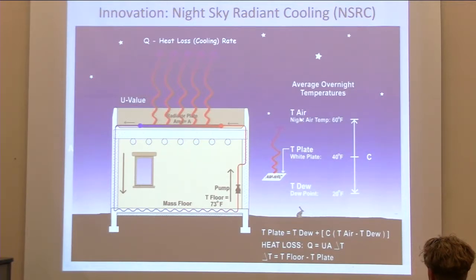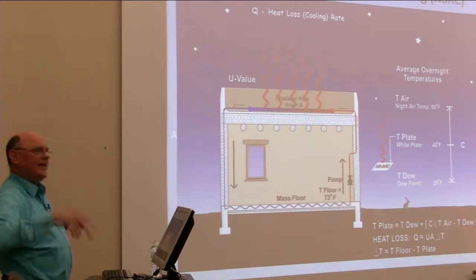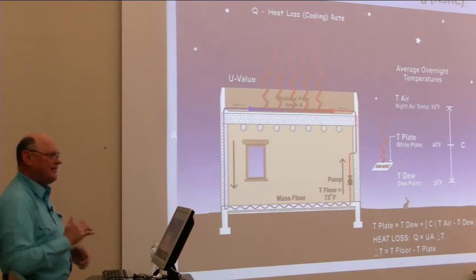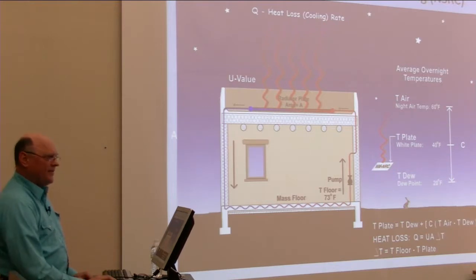You wait at night until the night is clear enough so that the plate temperature on this collector, the black surface on the collector, radiates away its heat to the night sky, and it radiates it so much faster than the air can reheat it that the temperature of the surface of the metal plummets. And you've probably seen this effect on the surface of your car hood or the top of your car. In the morning you come out and there's frost or dew all over your car, but nowhere else. Why is that? It's because your car was facing the night sky. The metal got so cold that it made dew condense out of the air, way colder than the air temperature.